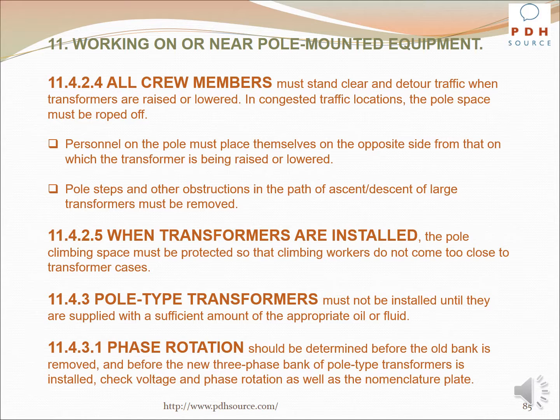All crew members must stand clear and detour traffic when transformers are raised or lowered. In congested traffic locations, the pole space must be roped off. Personnel on the pole must place themselves on the opposite side from that on which the transformer is being raised or lowered. Pole steps and other obstructions in the path of ascent-descent of large transformers must be removed.